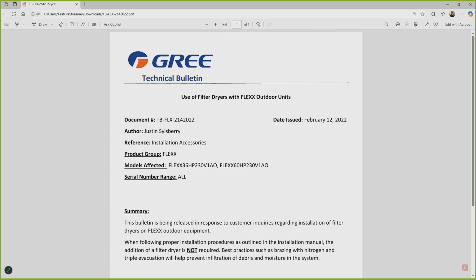Like I always say, when I get my oil changed, I hope they changed it with new oil. Again, it's not really there for that. Yes, if the debris isn't large enough to get caught by the fine mesh, it'll get caught, but we call it a filter dryer, why do we call it a dryer? Because it's there to remove moisture, not necessarily for all the debris and stuff. So if you're pulling a proper vacuum and following all your best practices, you shouldn't need a dryer in the system to begin with.